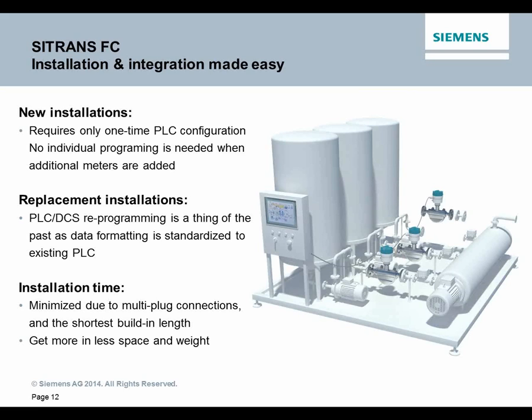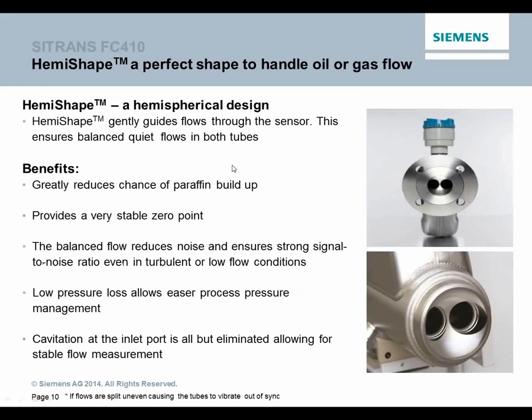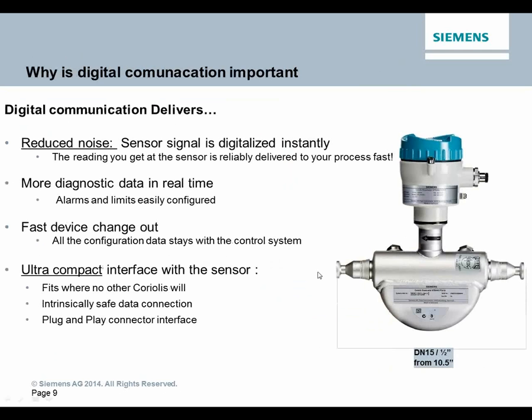These tubes have low spots and high spots. Now, you can set them up in a self-draining condition, but you can see that in the tube, and I'll actually go back to this guy. This is in a position in which you would be flowing liquid. Okay, so if you're flowing a liquid, you've got to bear in mind that you may have gas particulates in the stream, and that's the way the flow goes, like this.